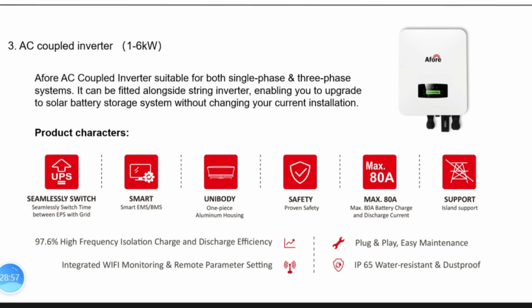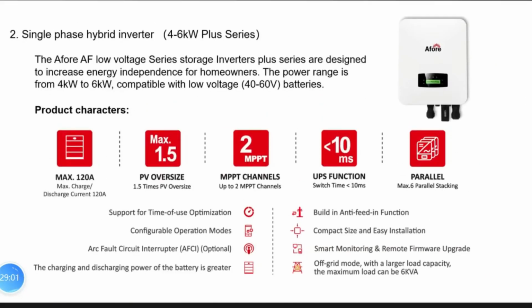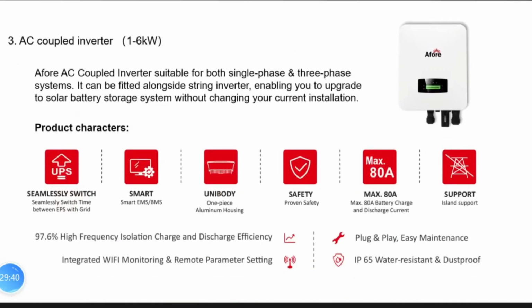So this is the AC coupled one. Compared with the normal inverter, the plus version has a bigger discharge and charge current, up to 120 amps. The plus version will charge the battery more quickly than the normal one, and deliver more power during off-grid mode. That's a major difference compared with the normal version. The AC coupled inverter has the same features as the single phase normal version and plus version. It's easier and more economic to add to an existing PV system, without changing the panel configuration and the variance.